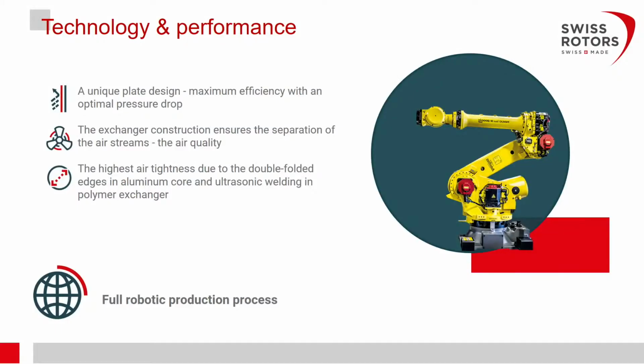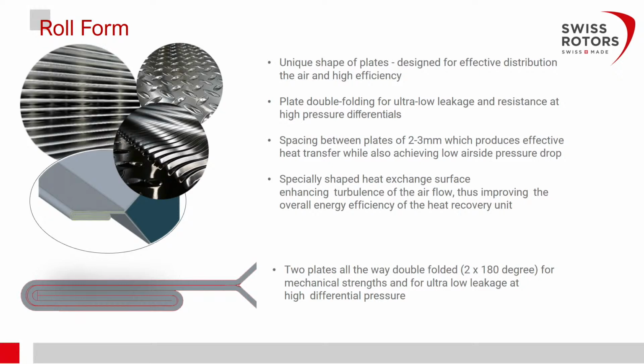Due to the fact that we are doing the double folding and everything is done by robots, we can ensure very high tightness, and there is very, very small internal leakage, almost nothing. The shape, as I mentioned earlier, was tested for a few months to reach the best possible. Usually in the middle part the shape is like waves in triangle shapes, and then external triangle parts give some embossing and also keep the distance between the plates. And in the left bottom corner, you see the fully double folded plates. We bend it 180 degrees twice. So it's much stronger compared to the others, which are not double folded.